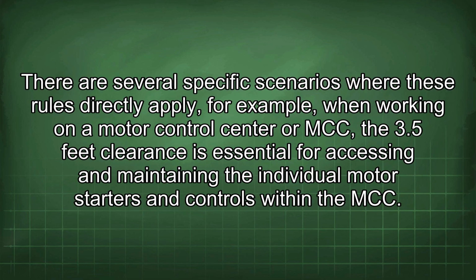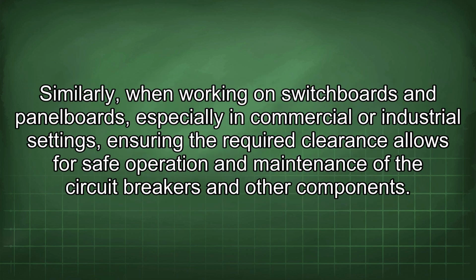There are several specific scenarios where these rules directly apply. For example, when working on a motor control center or MCC, the 3.5 feet clearance is essential for accessing and maintaining the individual motor starters and controls within the MCC. Similarly, when working on switchboards and panel boards, especially in commercial or industrial settings, ensuring the required clearance allows for safe operation and maintenance of the circuit breakers and other components.